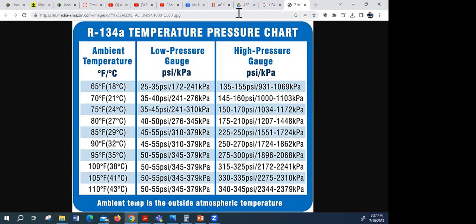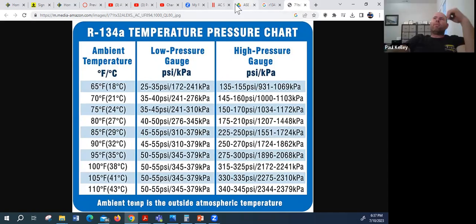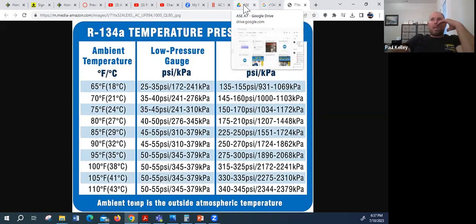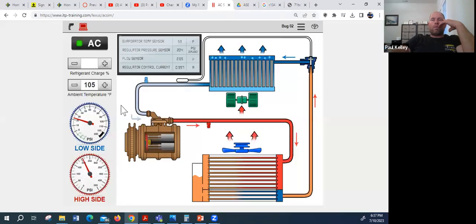Yeah, it's because it's 105 ambient. A lot of times when we're doing our test, it may be 90 or 85 or 80, and we're looking at 175, 210, 225, 250, maybe even as high as 270. But when you're up at 105 degrees, we should have substantially higher pressures. That's one of the things that can get a little confusing, is that's over 200 so you'd assume it's good, but you forget it's 105 ambient. It should be quite a bit higher.